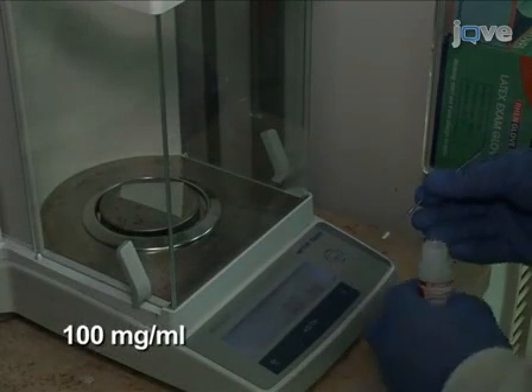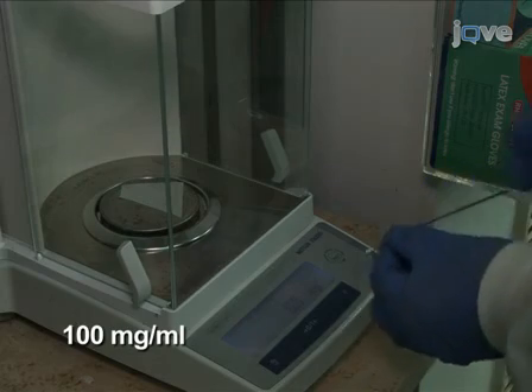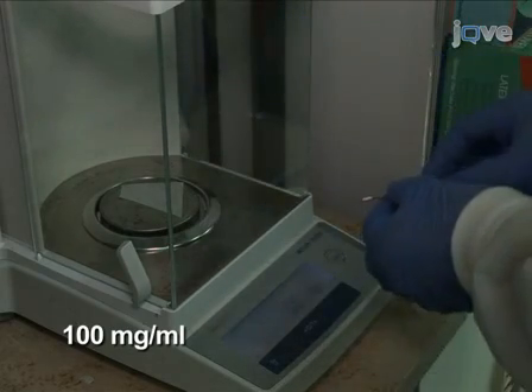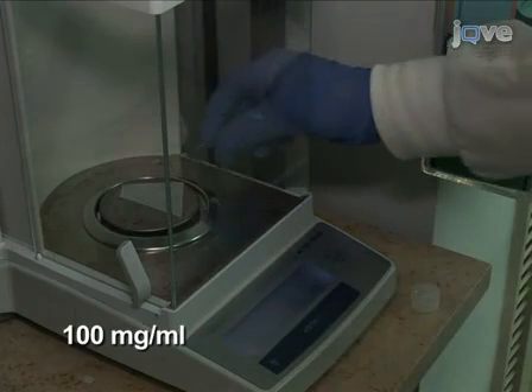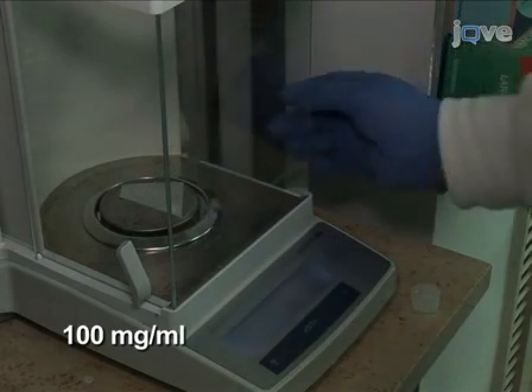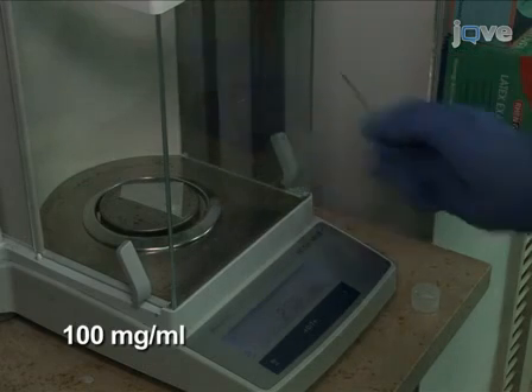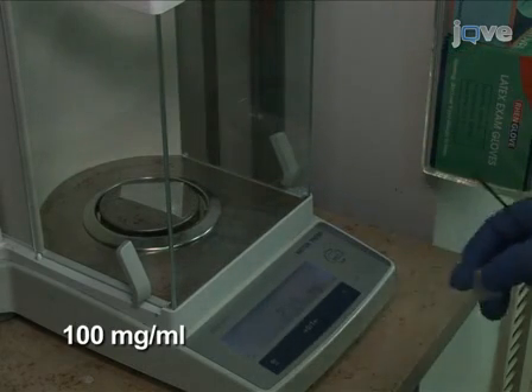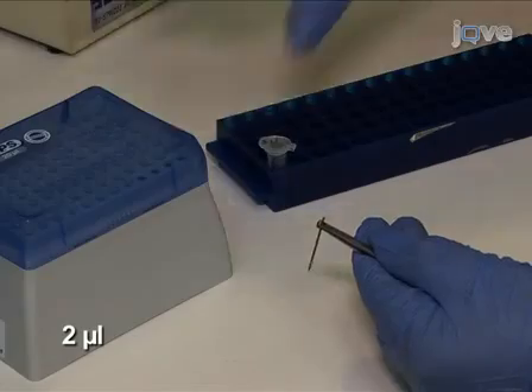First, prepare a 100 mg per milliliter solution of cesium iodide in purified water. Cesium iodide is used for high mass calibration as the singly charged salt clusters extend over a wide mass range, from 393 mass to charge ratio to well over 10,000.